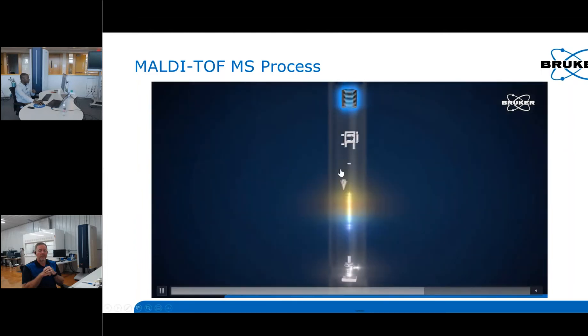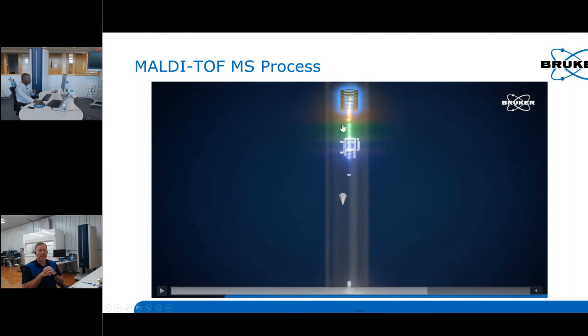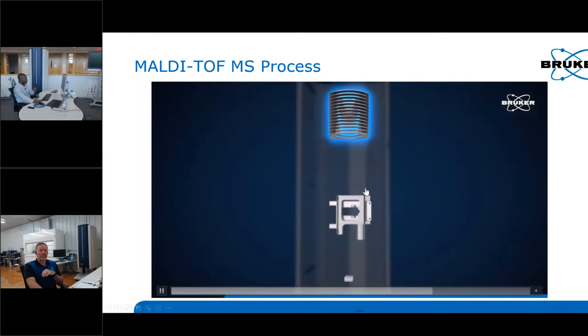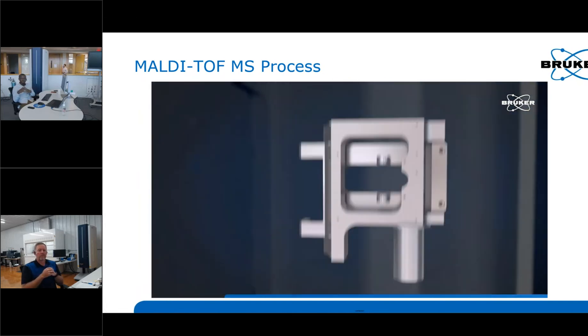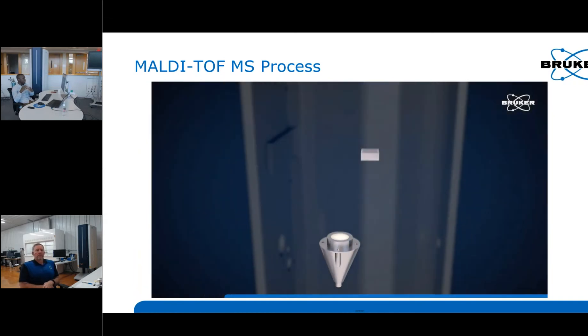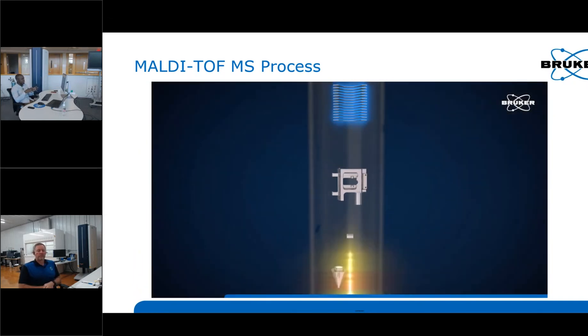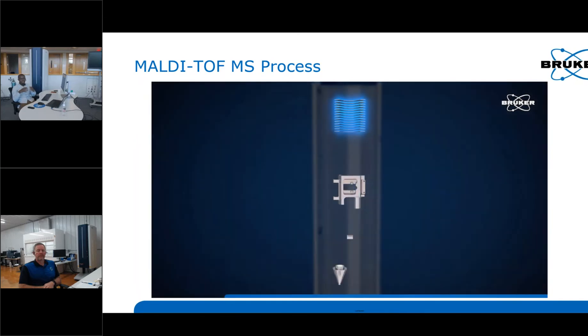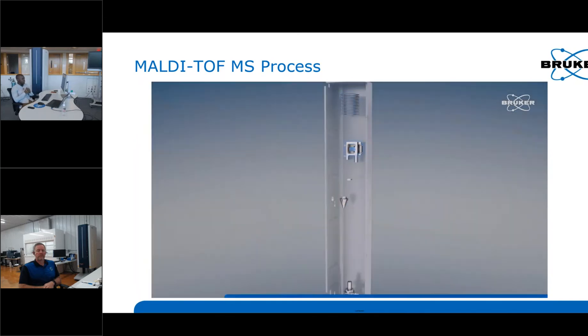In reflectron mode, there is an added element: reflectron plates are used to divert the ions toward a secondary detector. The combination of a longer flight path and the reflectron plates that help focus the ions onto the secondary detector results in higher resolving power in reflectron mode versus linear mode.